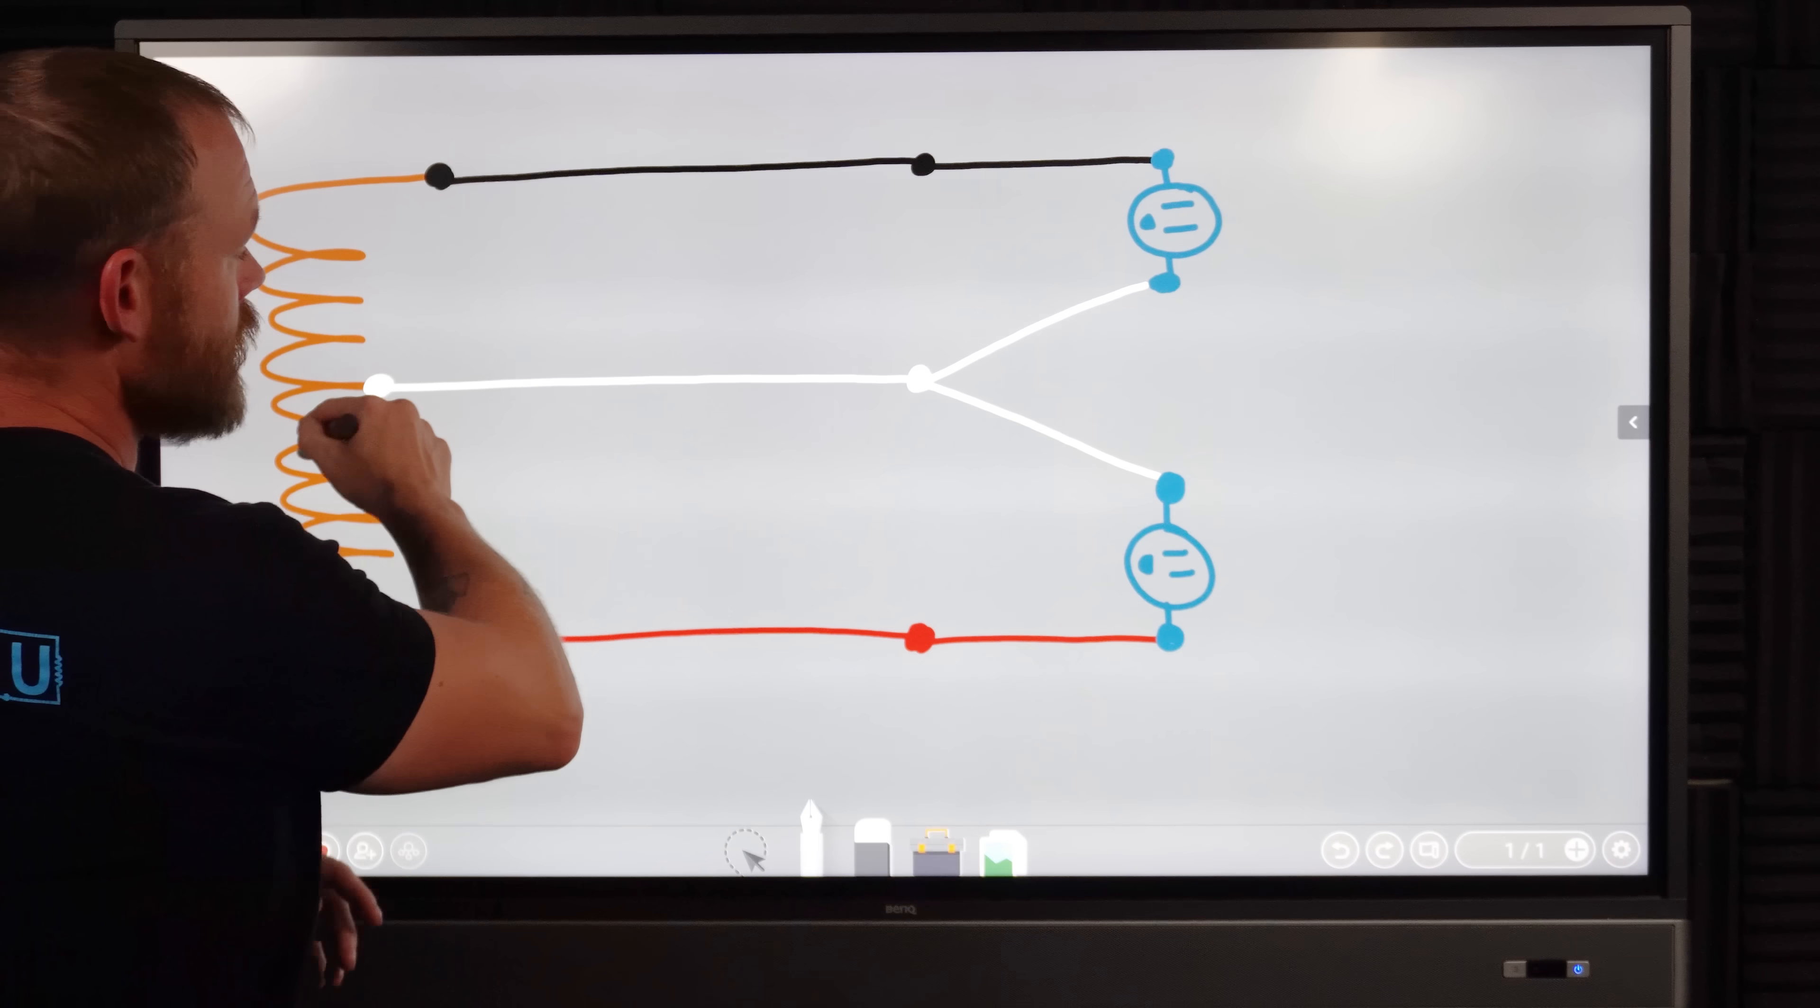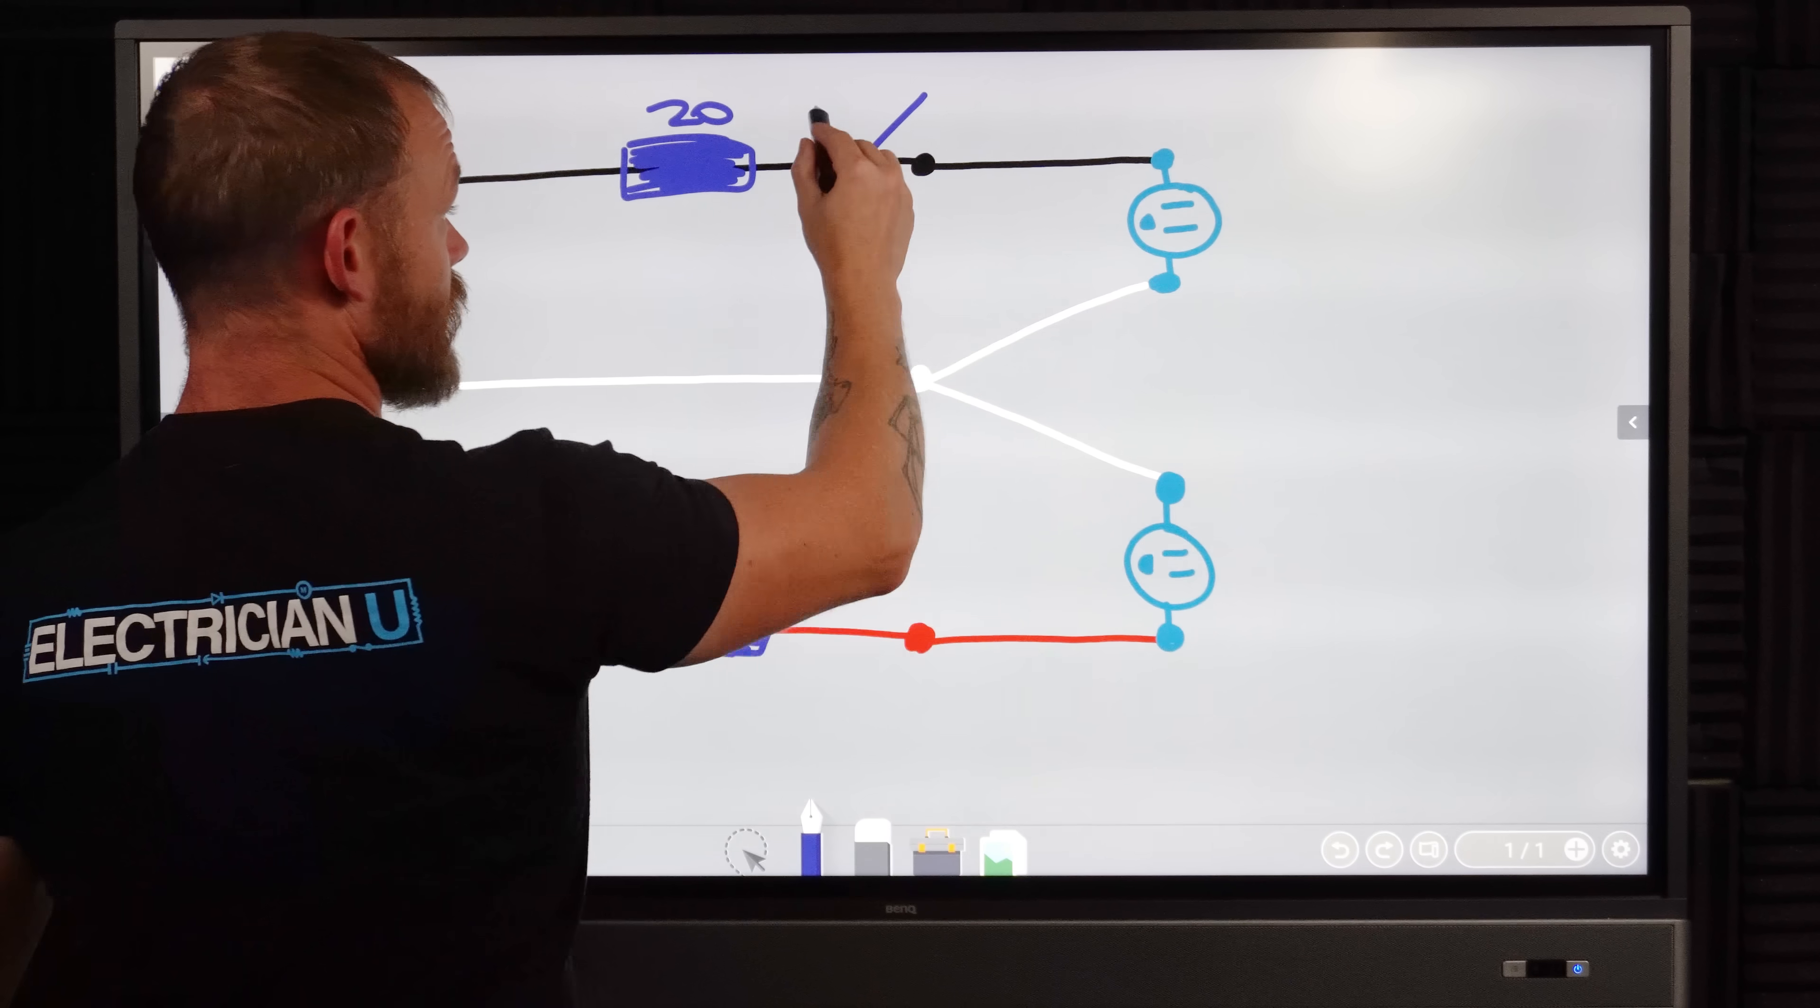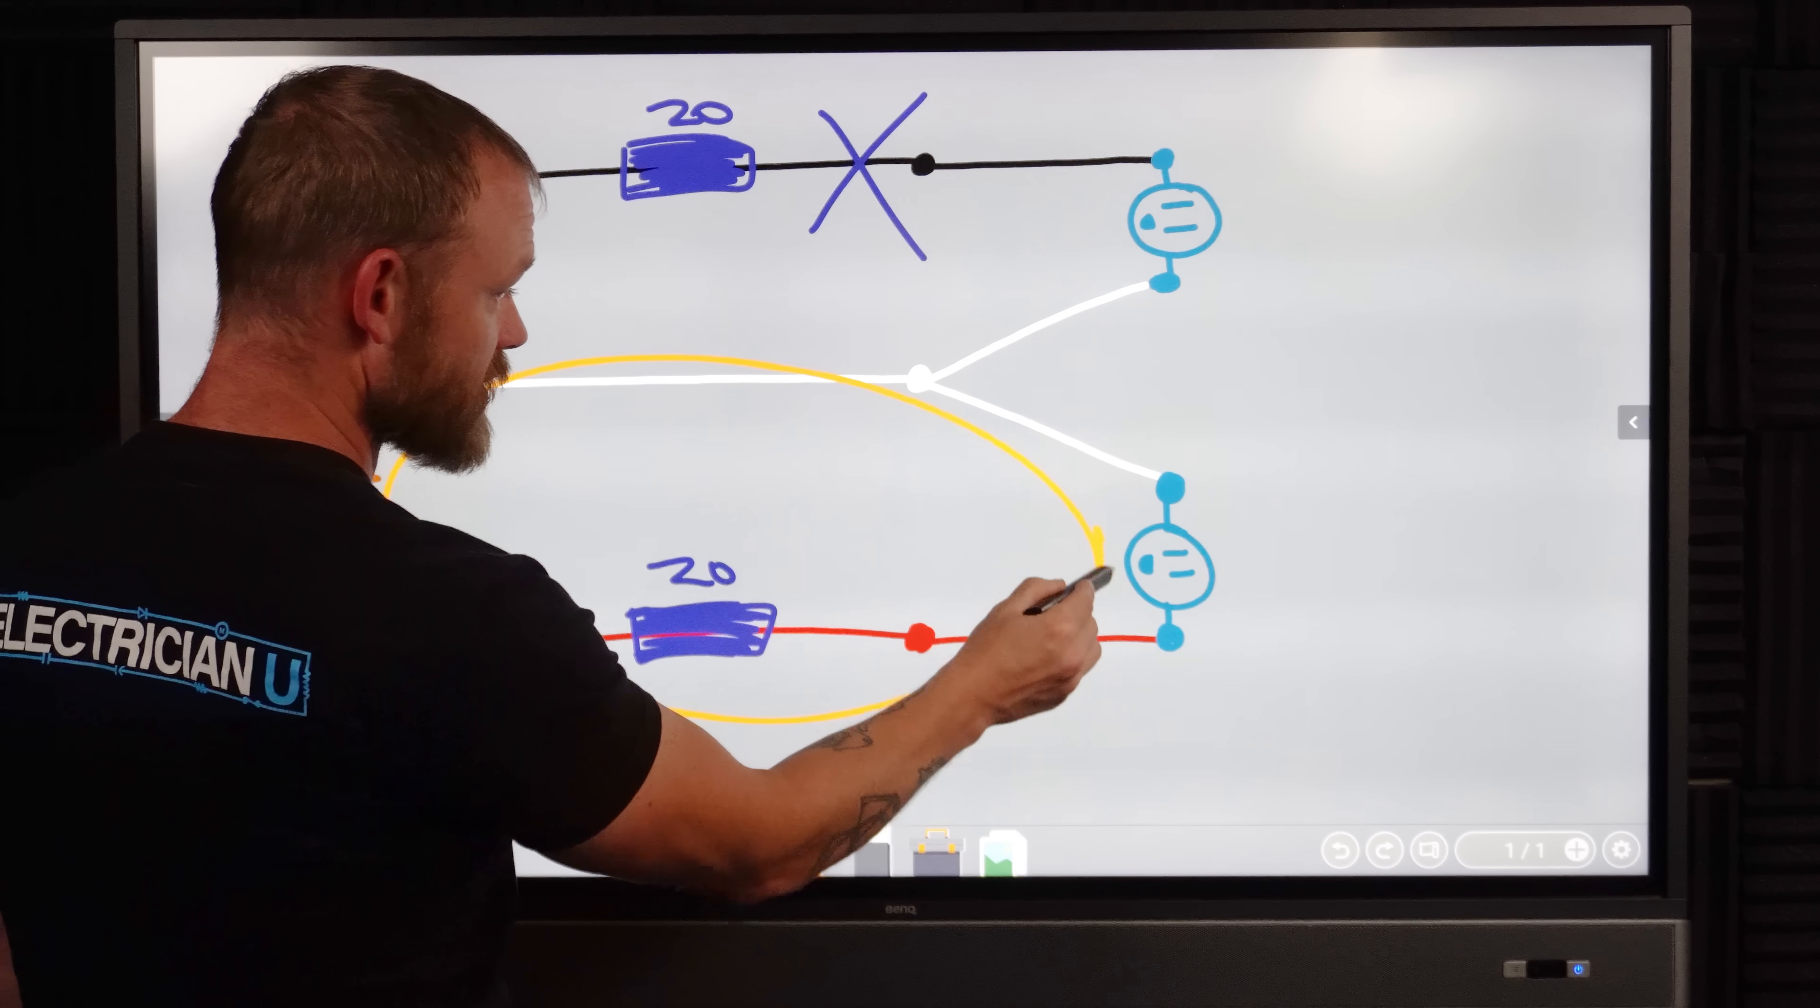We have a black and a white that go out and they share the same exact neutral. And then at a certain point, they split them out into two different things. So what happens is if we, say I've got in my panel, I've got a 20 amp breaker here and I've got a 20 amp breaker here. We don't ever have breakers on neutrals. So we flip the handle of this breaker and we assume this circuit is dead. So we go and we touch this neutral and we're like, oh yeah, I can touch the neutral. I can touch the black. Everything's safe. Right.